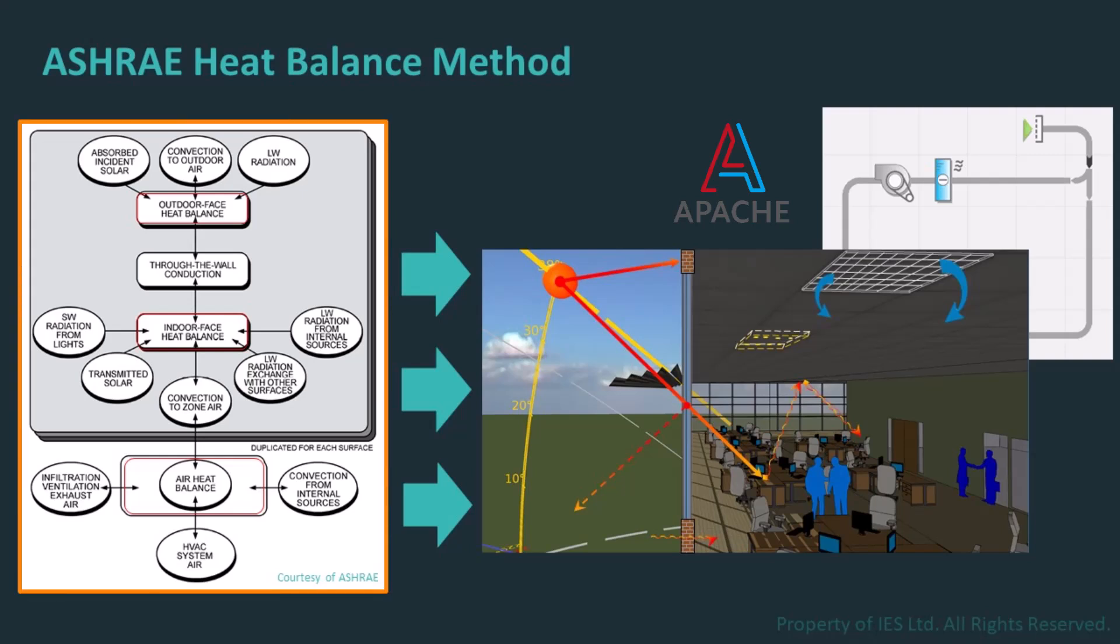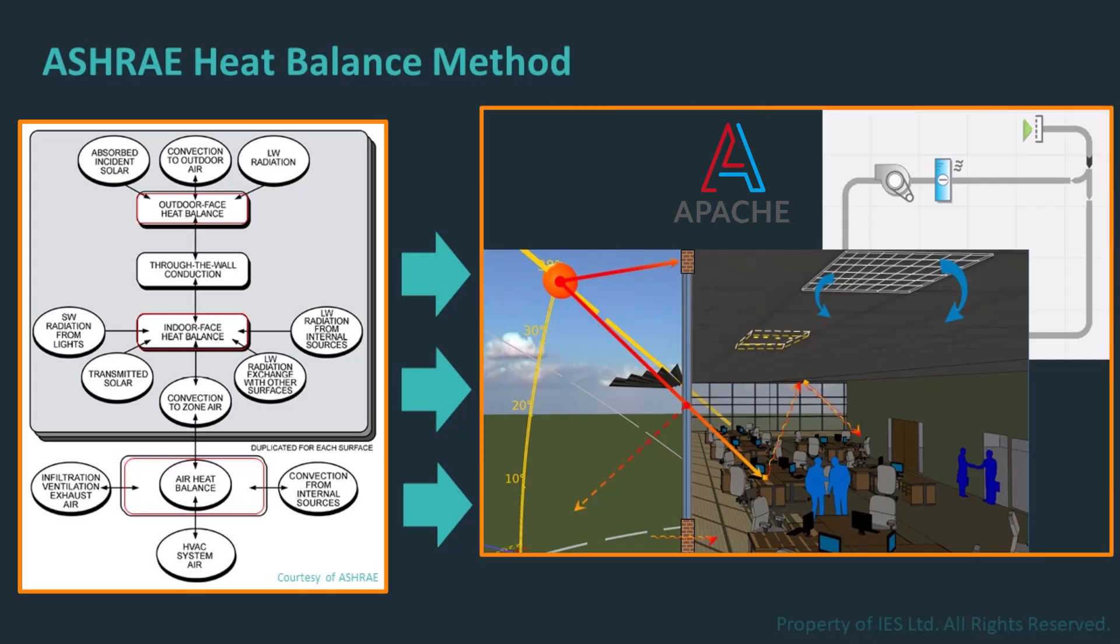Apache HVAC essentially fills the gap in the dynamic heat balance method beyond load calculation. It looks at how to deal with the dynamic heating and cooling loads for each hour to assess the energy necessary to maintain the desired indoor operating conditions. It allows for the sizing of specific HVAC equipment such as fans, pumps, boilers, chillers, etc., and it also allows for the detailed analysis of energy costs and carbon impacts associated with design choices associated with mechanical equipment selection.